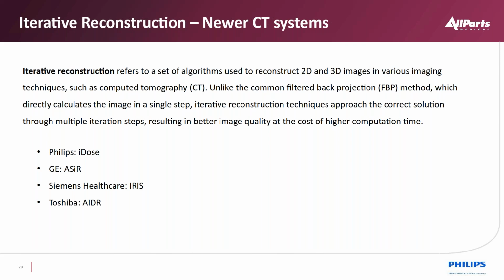When we do image quality testing on CTs, we don't use this because this is a variable that can change. But when we are looking at patient data, we want to lower dose. So I can use this function to lower the dose and maintain the same amount of noise, or I can use this at the same mA and increase the image quality. So it allows us to use it in two ways, which is what the radiologist at the hospital will decide to do with the protocols.